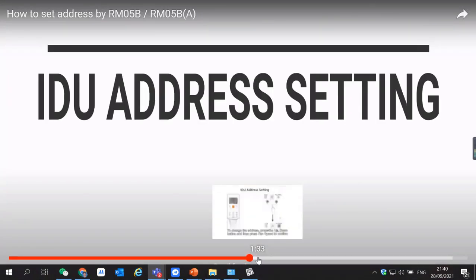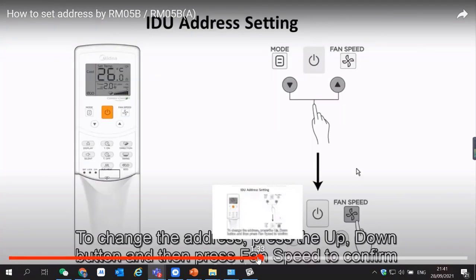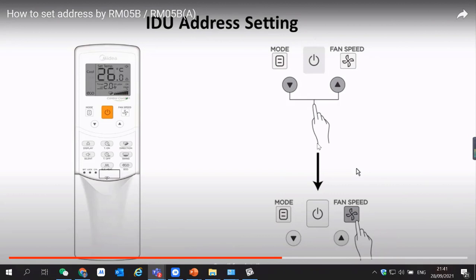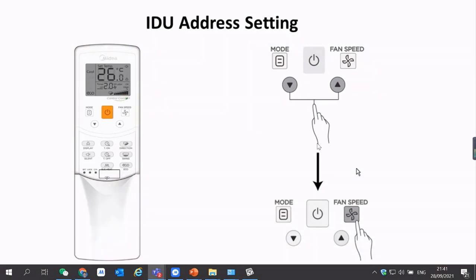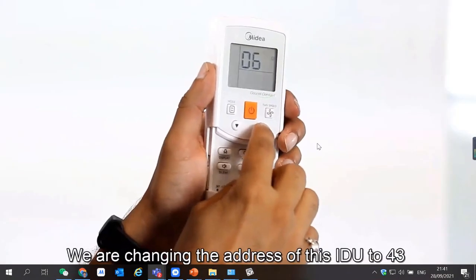Now if I want to change the address of this indoor unit, how to do that? Again, you need to enter the address setting mode and then press the power button. And if you press the up down buttons, then the address written on the controller will change, and you press the fan speed, this address will be sent to the indoor unit.